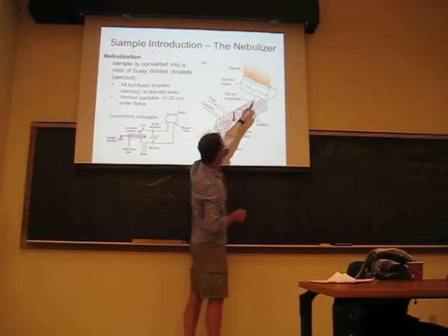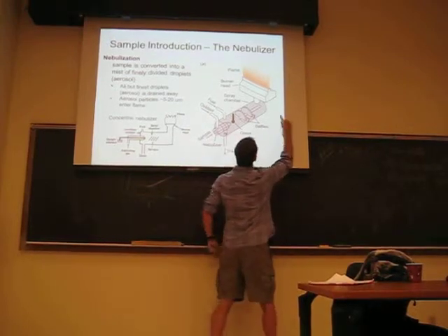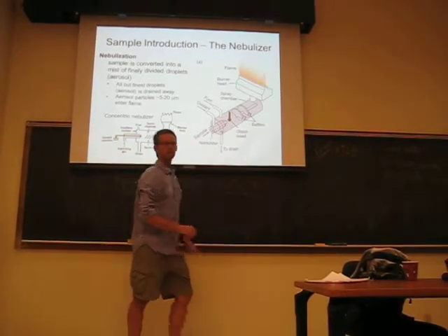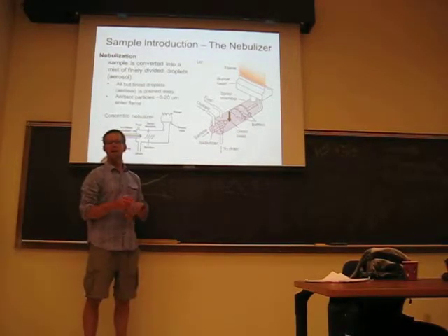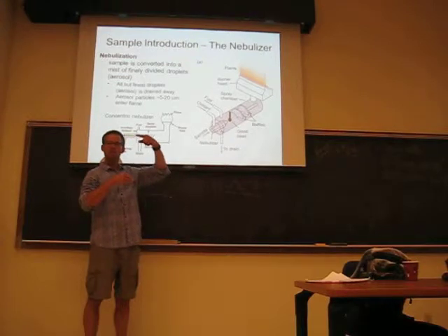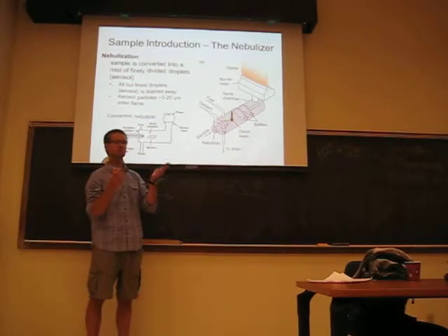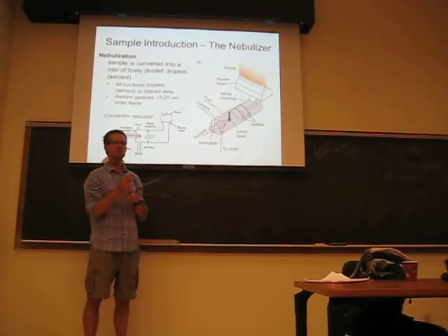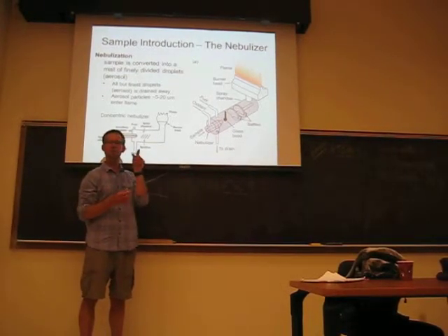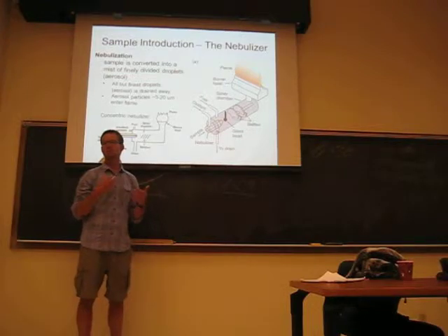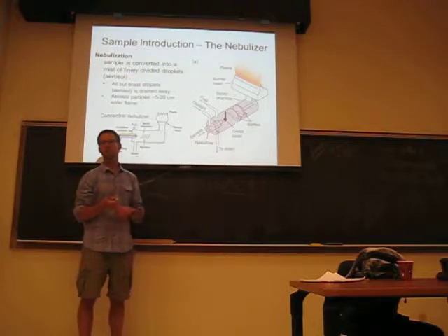And then that sample passes up there, and it passes through that flame, and your light beam, like I said before, is coming parallel to the burner head, and it's only there for less than a fraction of a second. So you're constantly aspirating sample while you're making the measurements of absorbance. You might set your program up to take 5 or 10 measurements and integrate the measurement over half a second or 0.2 seconds. So it may only take you 2 or 3 or 4 seconds to make the measurement, but you'll be aspirating stuff up for maybe 15, 20 seconds.